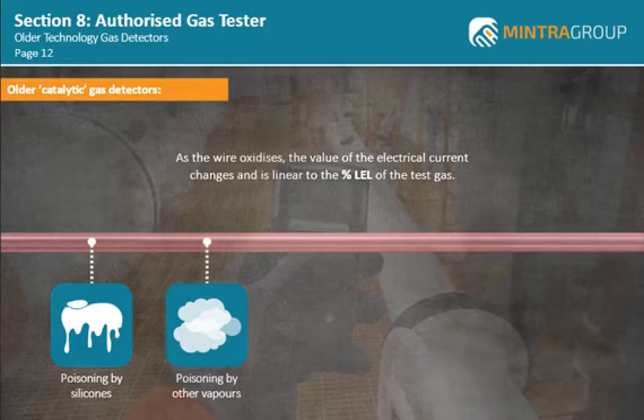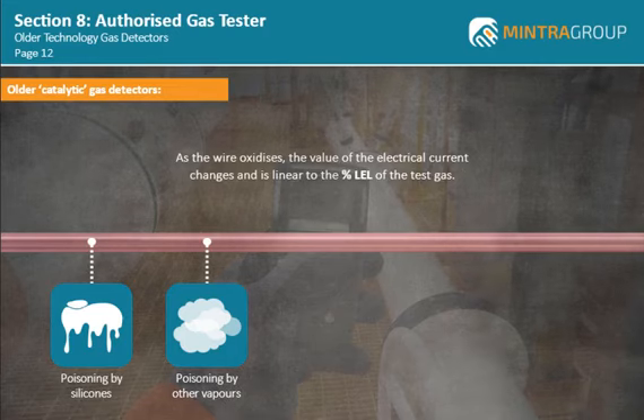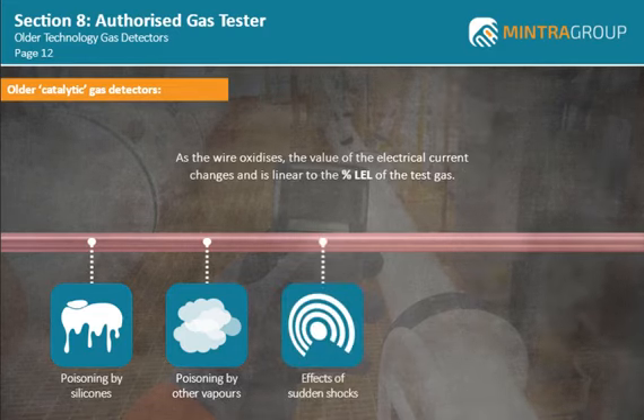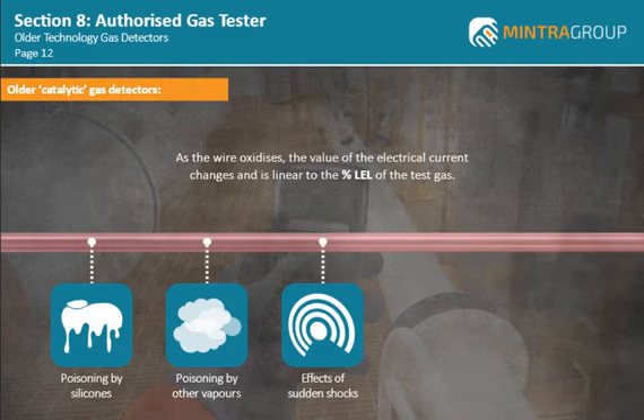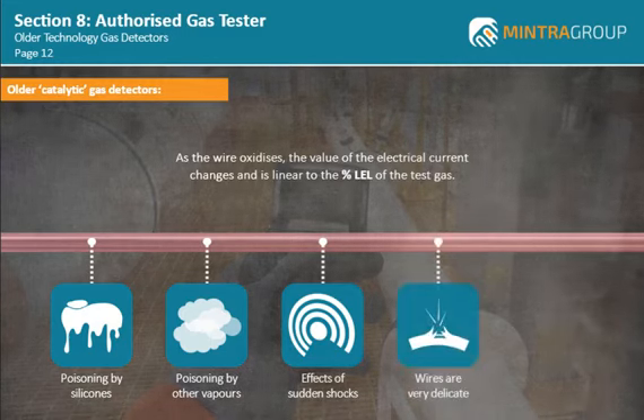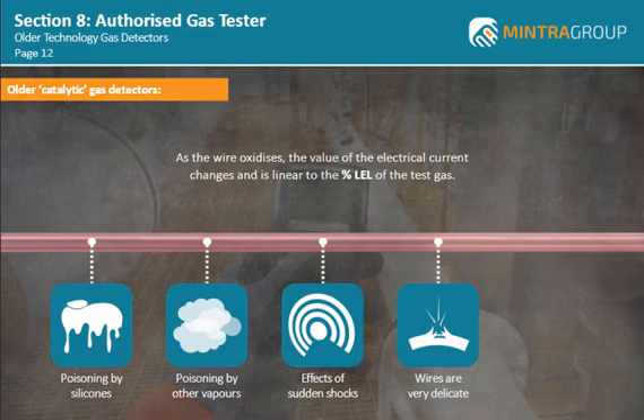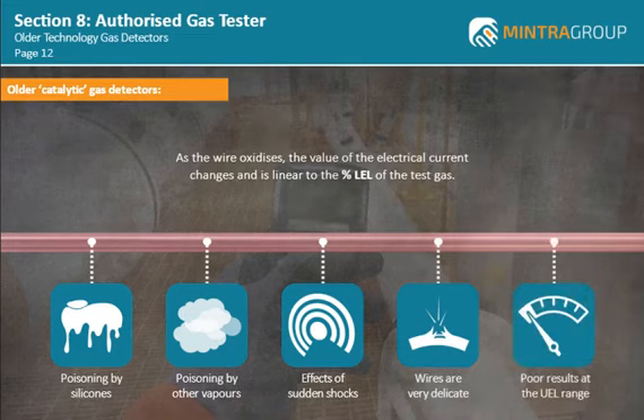Another drawback of these older models is that they are susceptible to the effects of sudden shocks if they are knocked against plant and equipment or dropped. The platinum wires are very delicate, and can easily be broken. The catalytic detectors also give poor results at the UEL range.